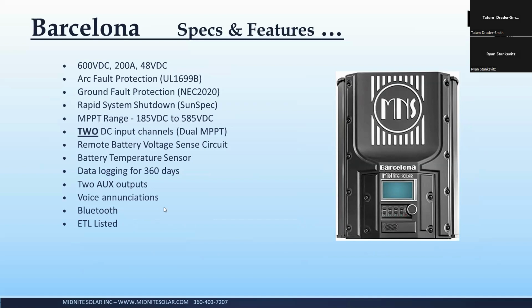It also has the remote battery voltage sense, which we really kind of beat on before, but this has that as well. And again, you only need one per system, and that's true of any sensor. So if you have a battery temperature sensor, a remote battery voltage sense, or a Whiz-Bang Junior, you only have to have one per system, and the system shares that data amongst everybody. If you accidentally install more than one, don't worry, the system will ignore all but one of those automatically. And it does also coordinate everything automatically. So all devices will go to float or bulk at the same time, or EQ or whatever you've got programmed in.